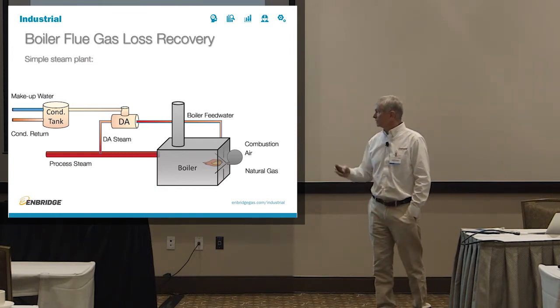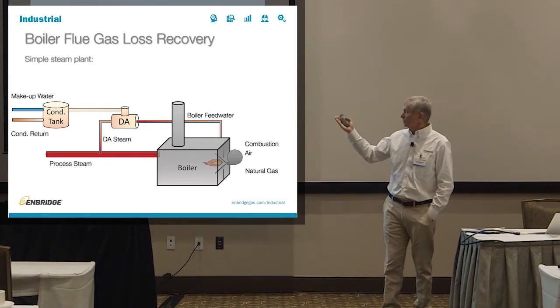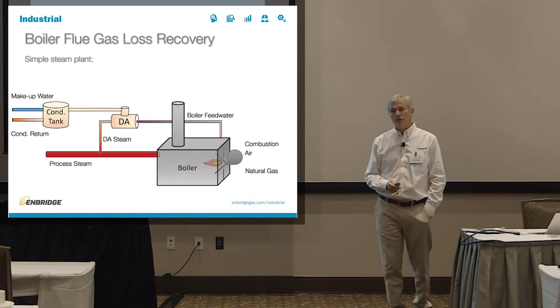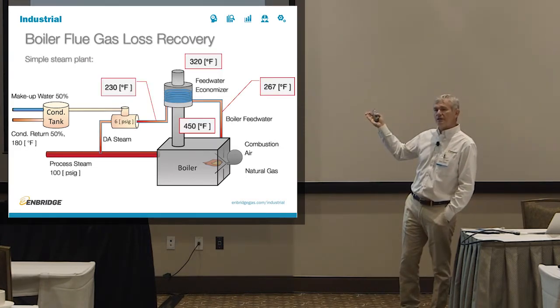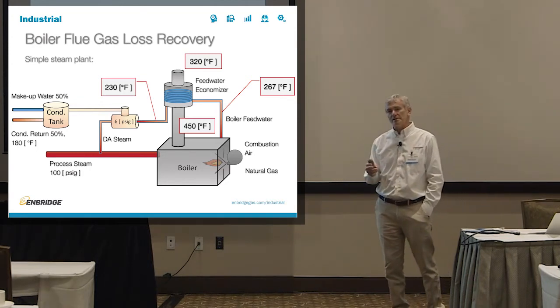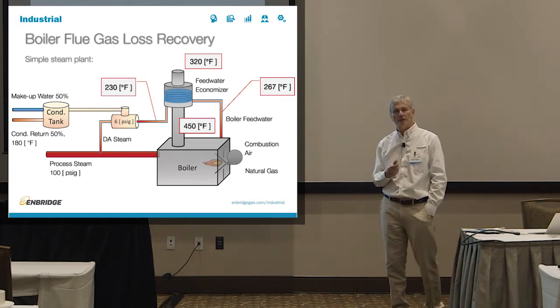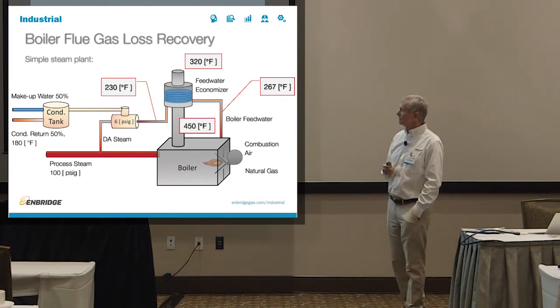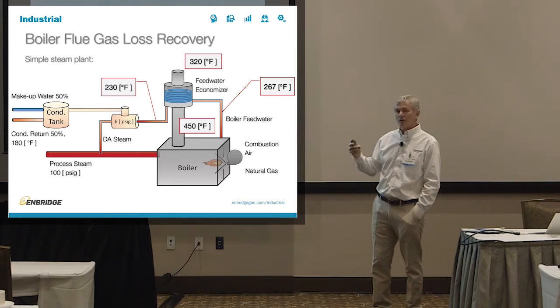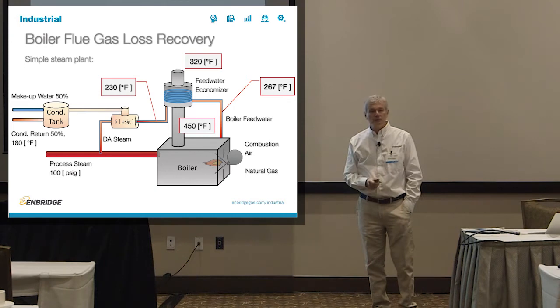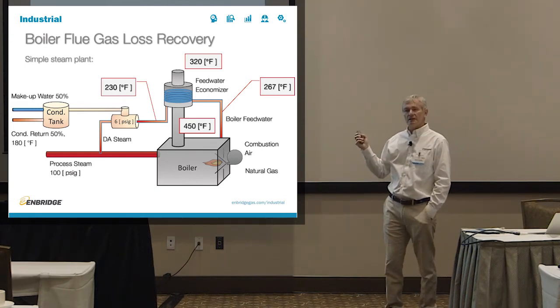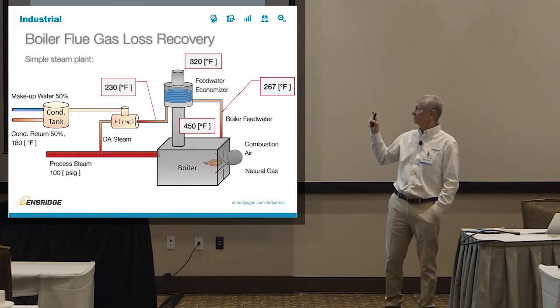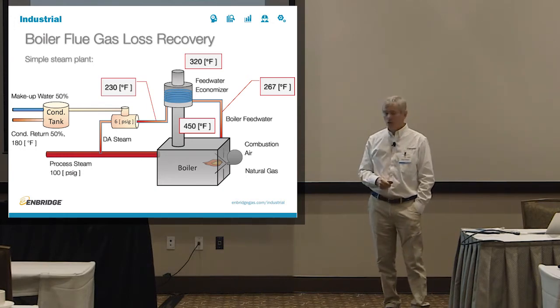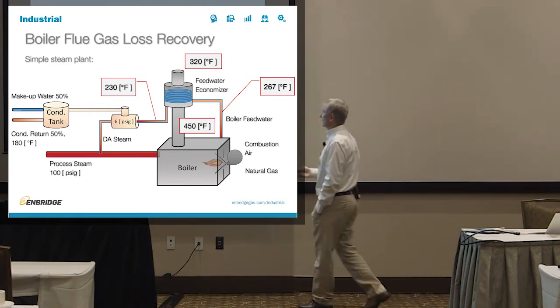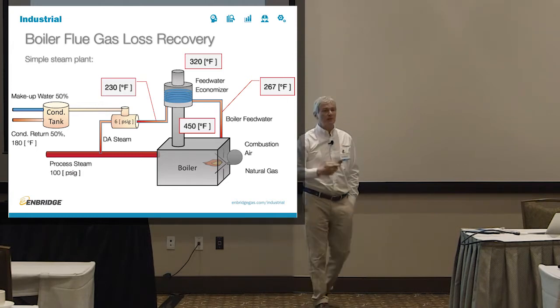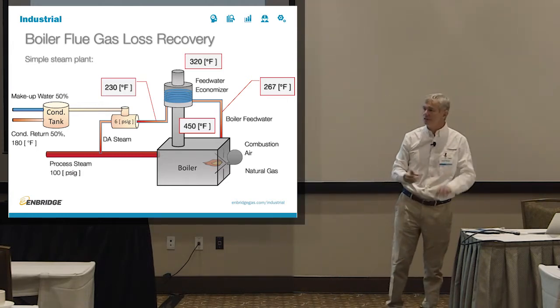But let's see how this works in real life. Let's say you have 50% condensate return at 180 degrees F, 50% makeup water, 100 psi steam and 6 psi in your deaerator. You will generally have about a 450 degrees F boiler stack temperature. If you put a feed water economizer into that stream, you can recover some of the heat from that 450 degree stream. Instead of going directly into the boiler, the deaerator stream goes through the feed water economizer. At 6 psi it'll be about 230 degrees F, but it'll be 267 degrees F once it leaves the economizer. So you gained about 37 degrees F from the waste heat. And now instead of the exhaust gas being 450 degrees F, it's 320 degrees F. So you reduce the amount of energy you're wasting, and you recovered some through the stream.